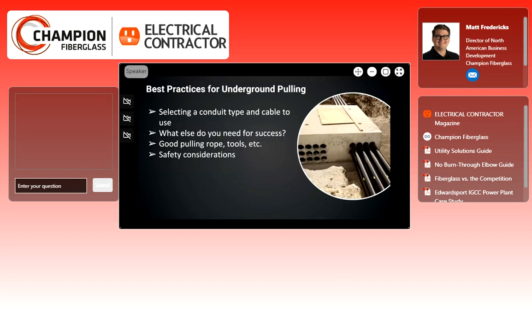And then safety considerations. Pulling underground, since the conduit is more than likely buried or in concrete slurry already, reduces the danger compared to pulling overhead with stringing where a conductor or rope is heavily exposed. But if you're pulling too hard, or haven't inspected your rope, and the rope breaks, it may pull out of the conduit system and come back at a 180-degree angle toward you. Always follow best practices from your pulling equipment manufacturer and any safety training you've done, and make sure your time in the trench is limited as well.